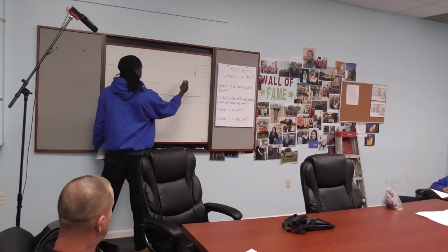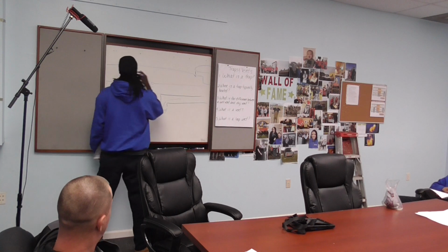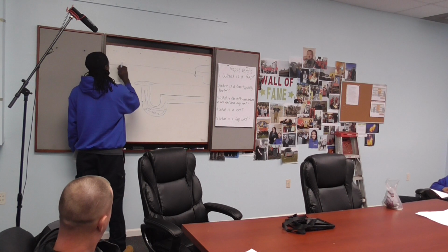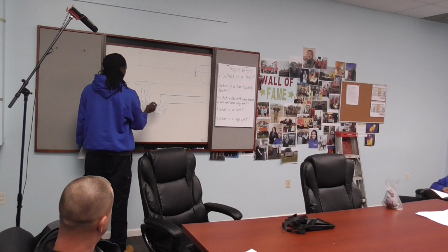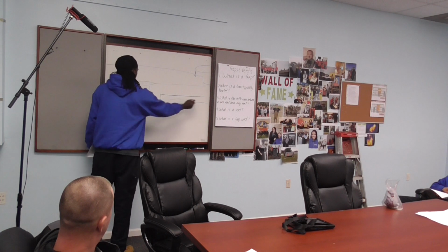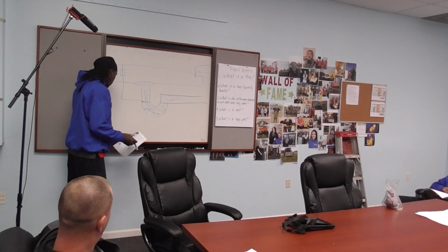But what this does is, we use the toilet a lot. You flush the toilet all the time. So when you flush the toilet, it detects that negative pressure and starts sending water through this water line and into your trap primer. It doesn't matter how much water it produces, because it'll just go down the drain, but it'll raise this seal back up so that you won't get any sewer gases. That's what the trap primer is.